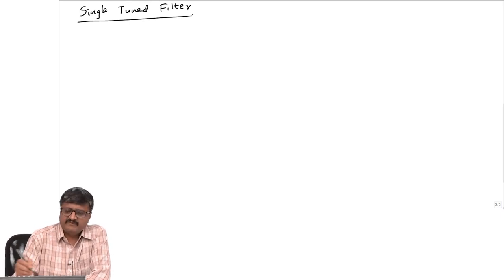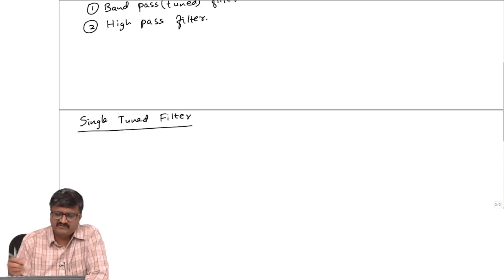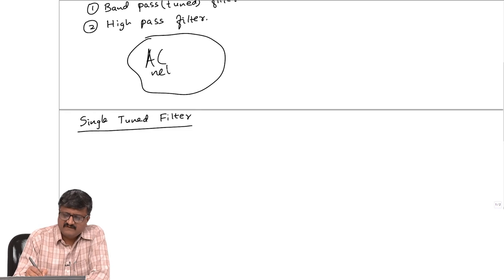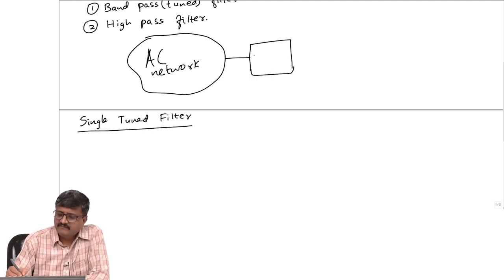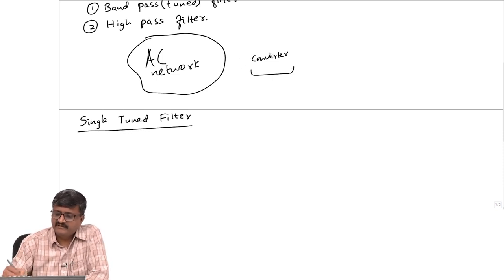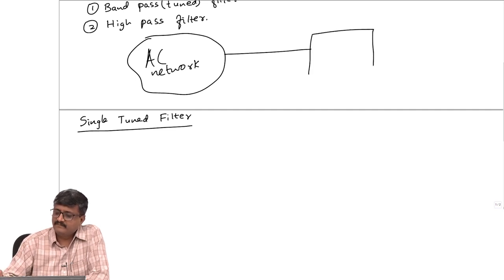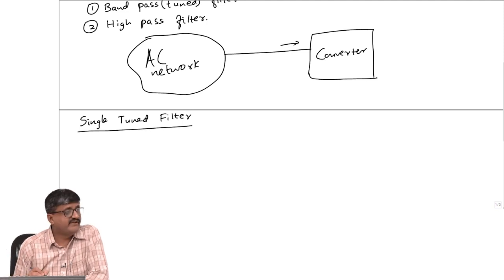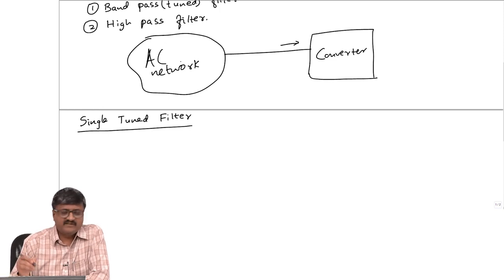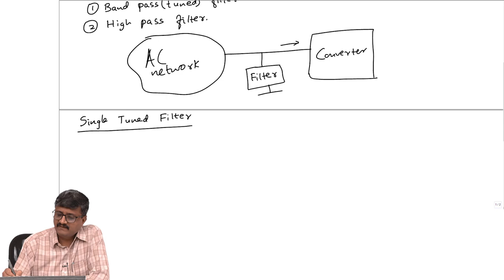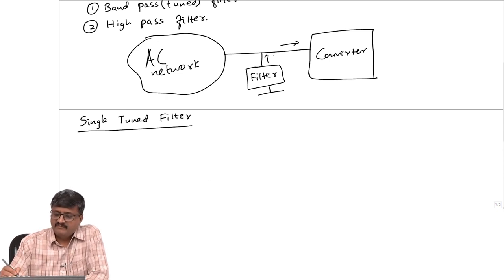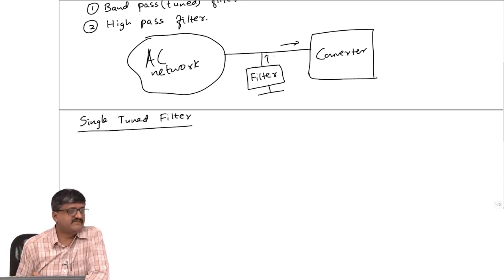So that it does not flow into the AC network. What I am trying to say is: suppose I have an AC network and a converter here. I provide a path — there are harmonics in the currents on the AC side of the converter, and if nothing is done, they will flow in the AC network also. If I provide a path in the form of a filter, the currents will actually flow through the filter and not through the network. That is the idea.